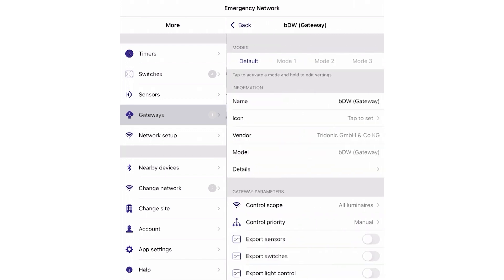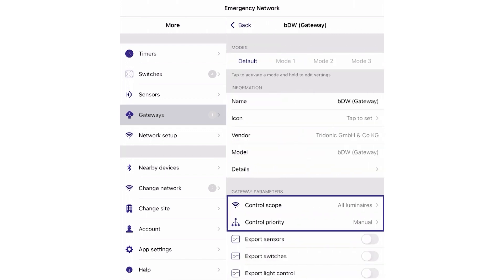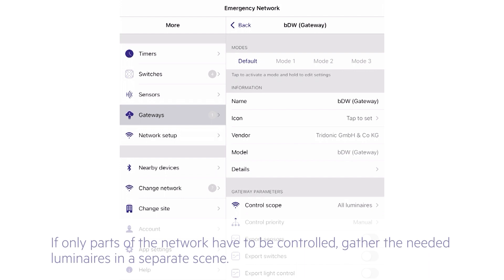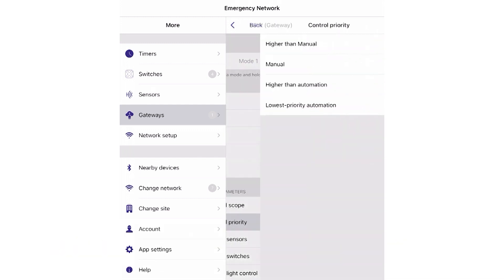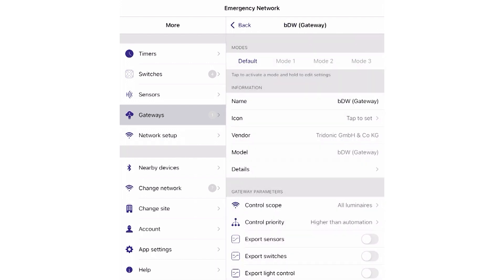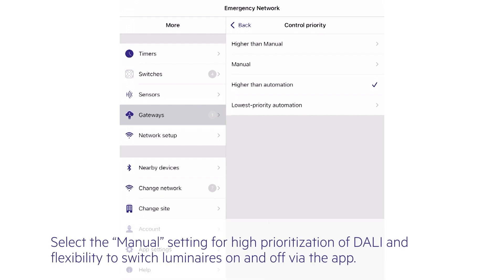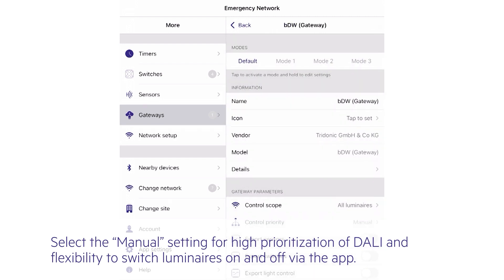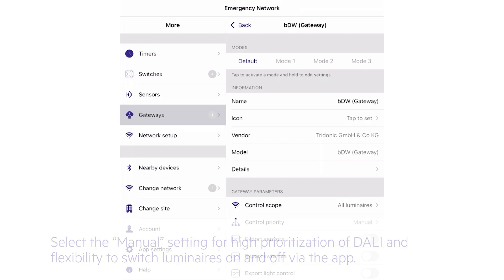Choose this device to get to the DALI gateway settings. In general there are only a few parameters to configure. The control scope defines what has to be transferred to the DALI line — in the shown example it's all luminaires. If it's necessary to control only a part of the network, it's possible to gather these luminaires in a separate scene to display only the luminaires of this scene on the DALI line. Next is the setup of the control priority. Depending on this setting, commands from the DALI bus are handled with higher or lower priority. Tridonic's recommendation is to select the setting manual. In this setting, DALI is prioritized as high but the user is still able to switch the luminaires on or off via the app.